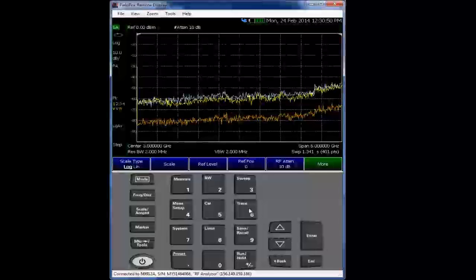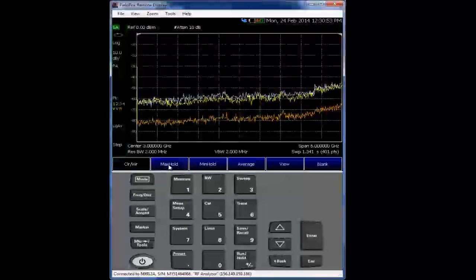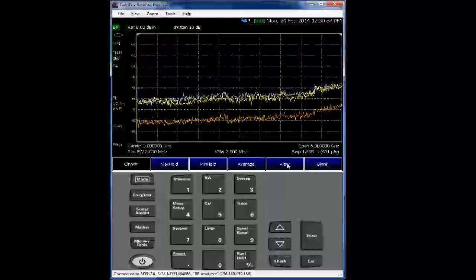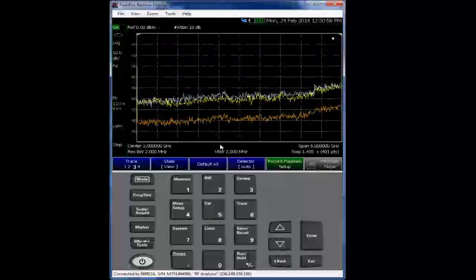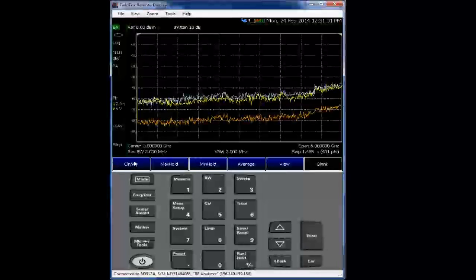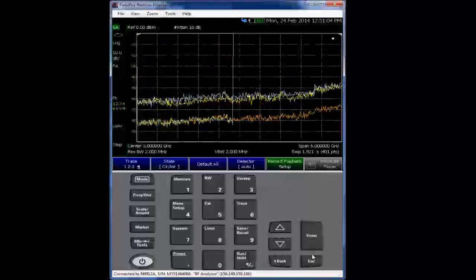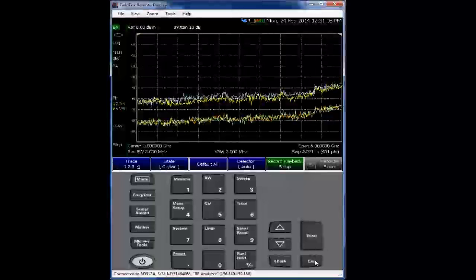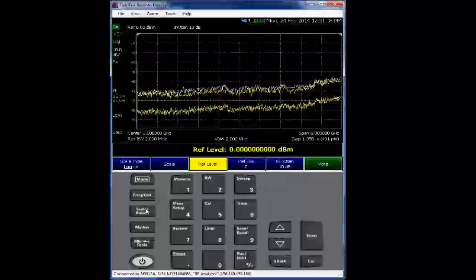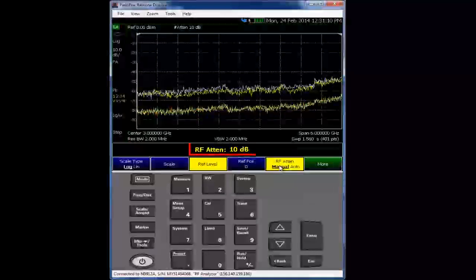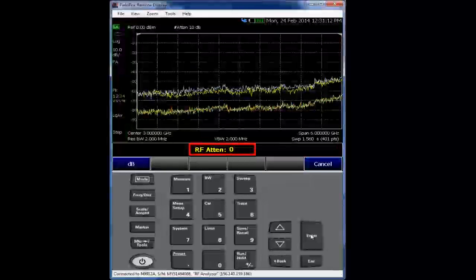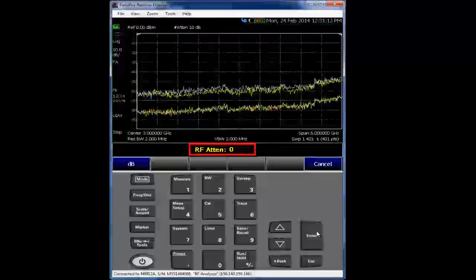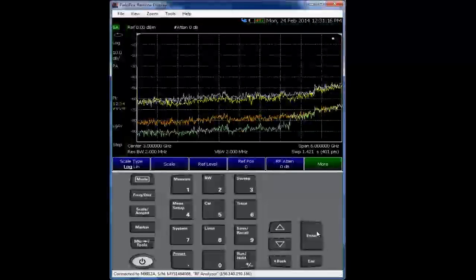The next thing we'll do is we're going to put this trace into memory, and we're going to optimize the attenuation to zero dB, the lowest displayed average noise level. And that's going to be with the input attenuator set to zero. So we'll go back into the scale amplitude, go into the RF attenuation, and rather than have it at 10 dB, we will put it at zero. And that'll be our dynamic trace, trace four.